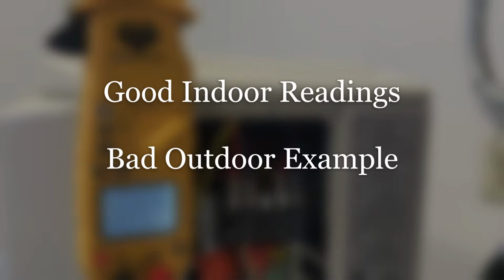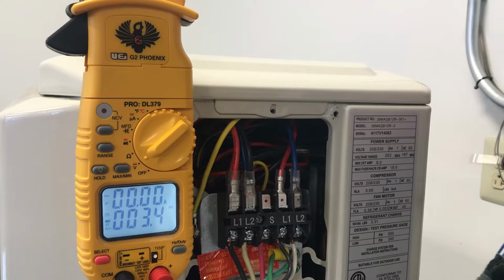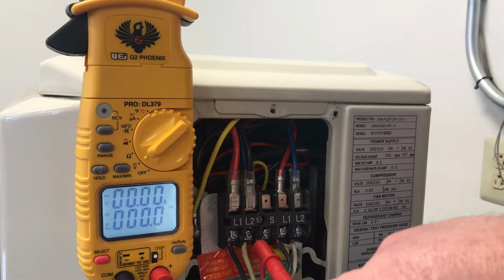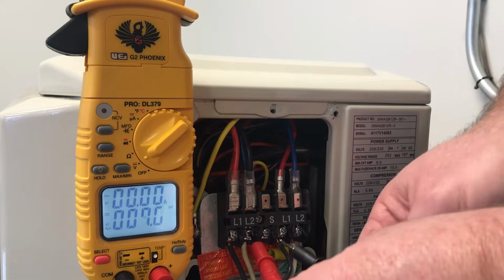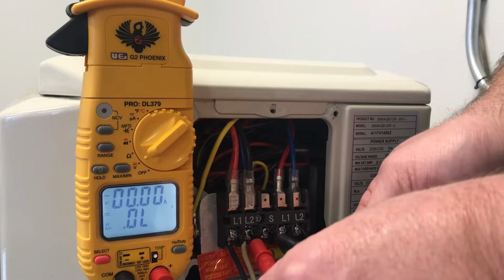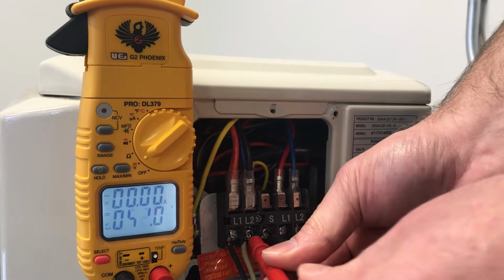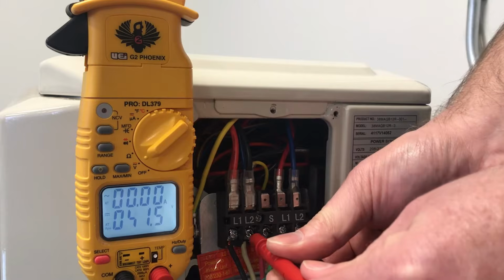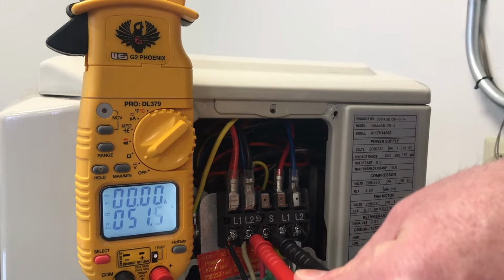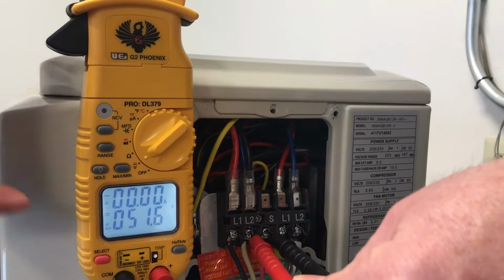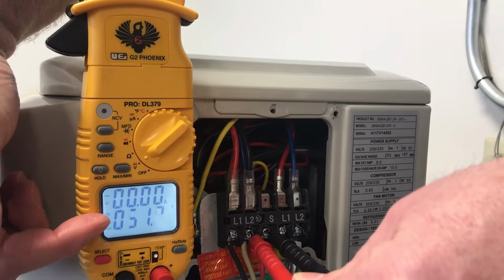Now we're going to show you what communication looks like with a unit that is not working properly. So we're going to do the same test. We're going to go from L2 with your red lead, S with your black lead, and now you're going to notice a different reading. It's still going to fluctuate, but as you notice, it never goes into a negative, and you would see that negative pop up right around here.